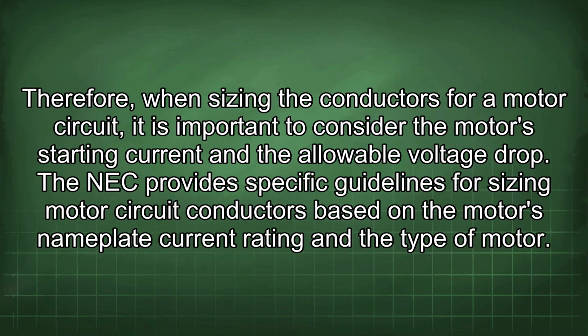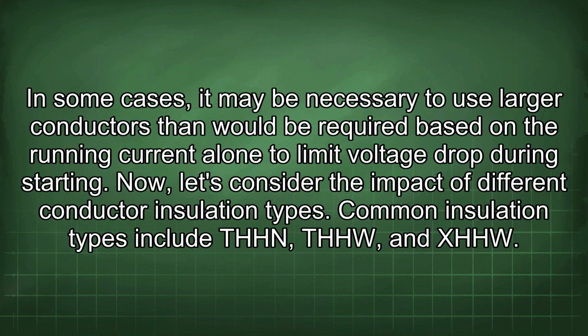Therefore, when sizing the conductors for a motor circuit, it is important to consider the motor's starting current and the allowable voltage drop. The NEC provides specific guidelines for sizing motor circuit conductors based on the motor's nameplate current rating and the type of motor. In some cases, it may be necessary to use larger conductors than would be required based on the running current alone to limit voltage drop during starting.